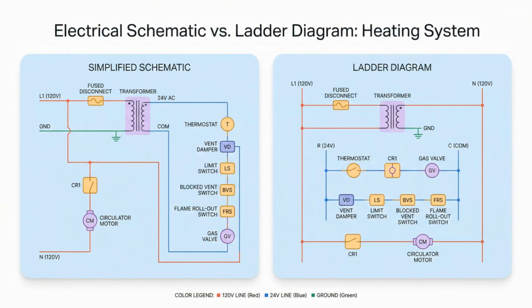Electrical wiring has to comply with the electrical authority and code. Manufacturers provide both schematic and ladder diagrams to show internal boiler wiring and to guide wiring for thermostats, zone valves or pumps, circulators, and safety devices. One common pattern is 120 volts feeding the boiler and circulator, and a transformer stepping down to 24 VAC for controls like the gas valve and thermostat circuit.